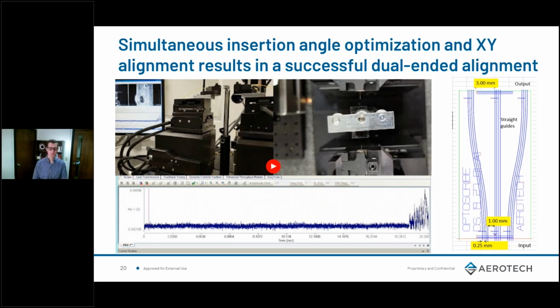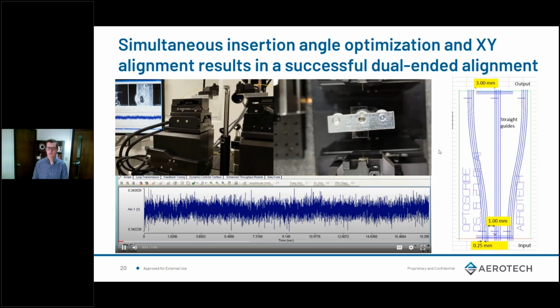So we're going to go ahead and we're going to perform an optical alignment here. You'll see the optical power measured from the analog voltage at the bottom of the screen here as the optimization goes. Keep in mind, this particular stack is not calibrated, so we expect, as we've done, plus or minus 20 to 30 microns of error over large travel moves. So I'm going to play this video and we'll see this thing happening.